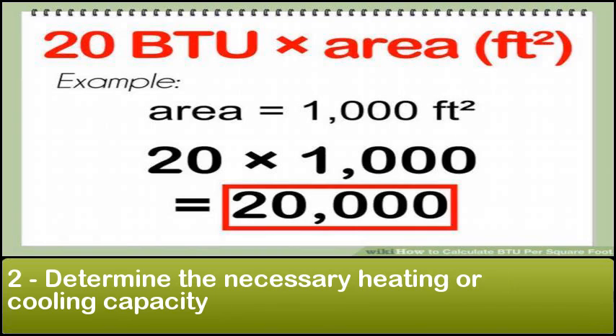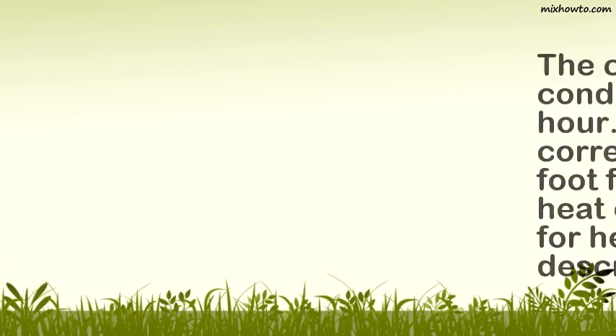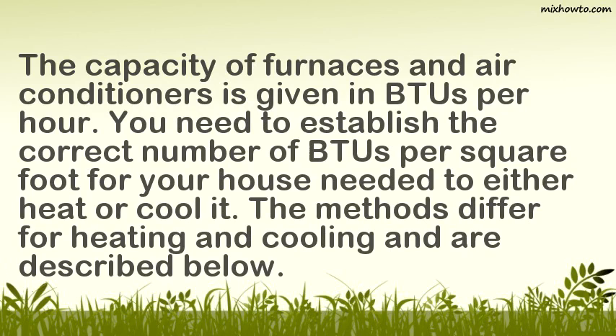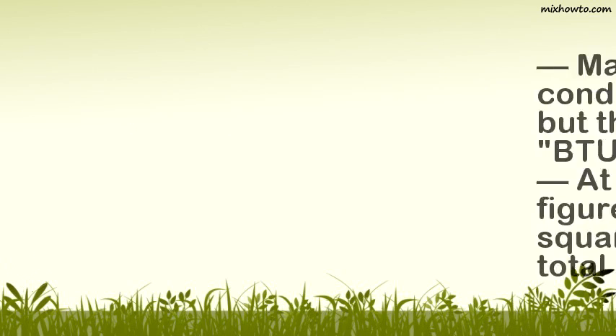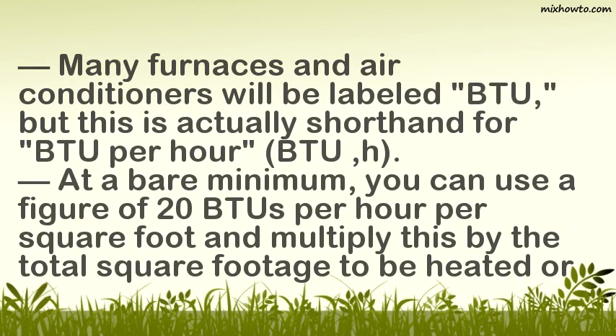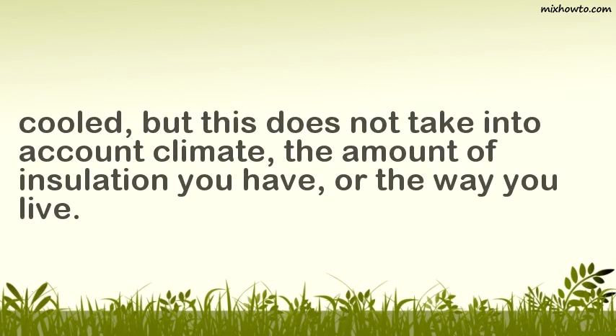To determine the necessary heating or cooling capacity: the capacity of furnaces and air conditioners is given in BTUs per hour. You need to establish the correct number of BTUs per square foot for your house needed to either heat or cool it. The methods differ for heating and cooling and are described below. Many furnaces and air conditioners will be labeled BTU, but this is actually shorthand for BTU per hour (BTU/H). At a bare minimum, you can use a figure of 20 BTUs per hour per square foot and multiply this by the total square footage to be heated or cooled, but this does not take into account climate, the amount of insulation you have, or the way you live.